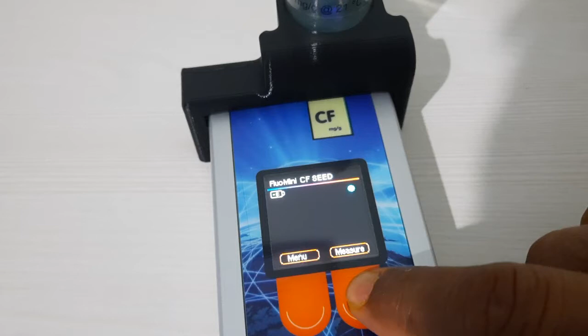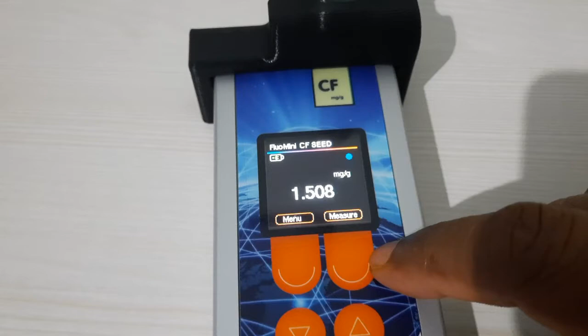Menu, go to sensor settings, enter. So 61, 62, so we'll keep it at 62. Next, set, enter. Next, set, exit, measure. Yeah, so it is almost coming at exactly. So this is how you do the calibration, right?